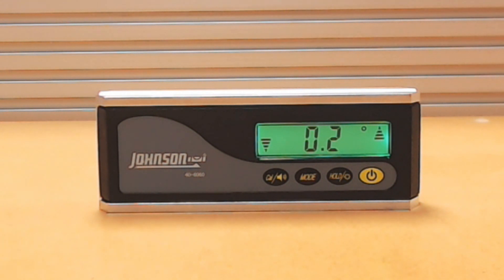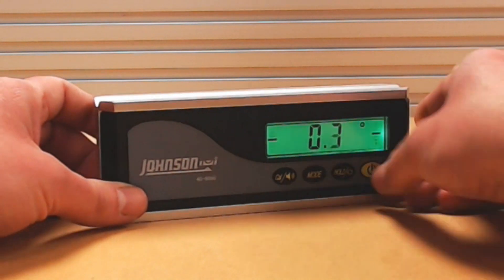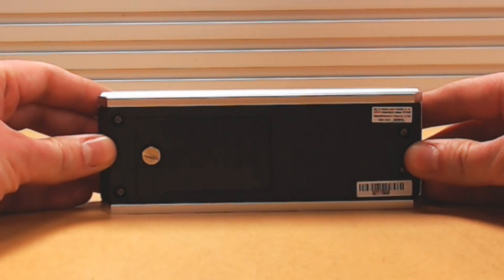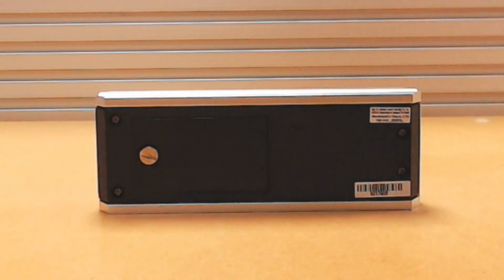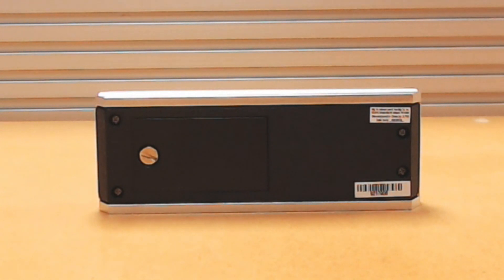Record the first measurement. Flip the inclinometer 180 degrees and record a second measurement in the same position.